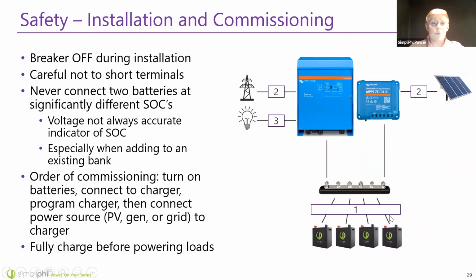Also, don't connect two batteries at significantly different states of charge. If you have an existing, fully charged system, don't just connect your brand new battery to it. We ship batteries out at about 30% state of charge due to safety regulations, and when they reach the customer they often think they're fully charged. That's not the case. You might even see a voltage of 52 or 53 when you first receive the battery, but that doesn't mean it's fully charged. Be sure to fully charge the batteries before connecting them all in parallel and before powering loads with a new battery.